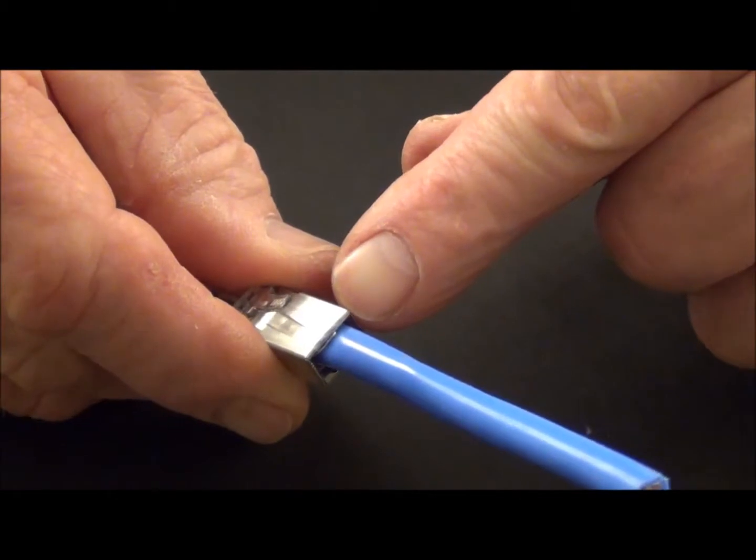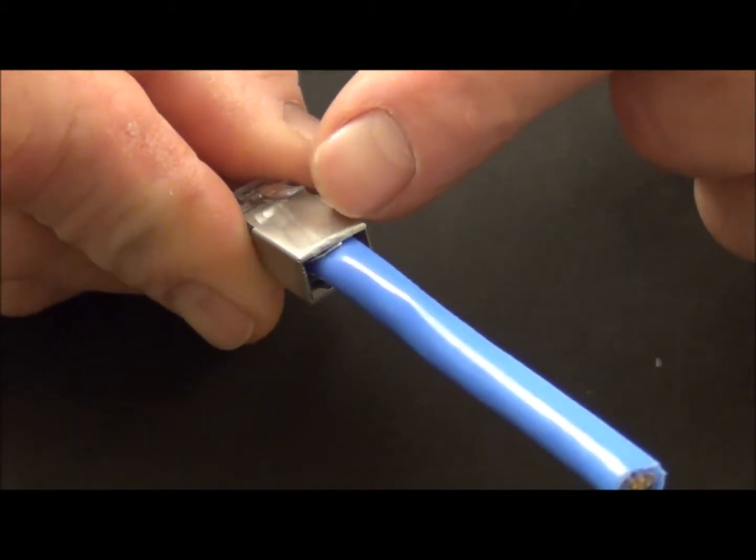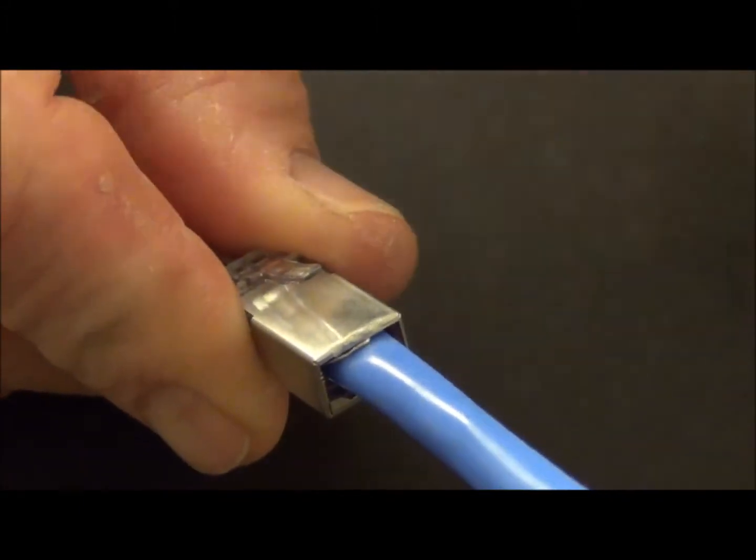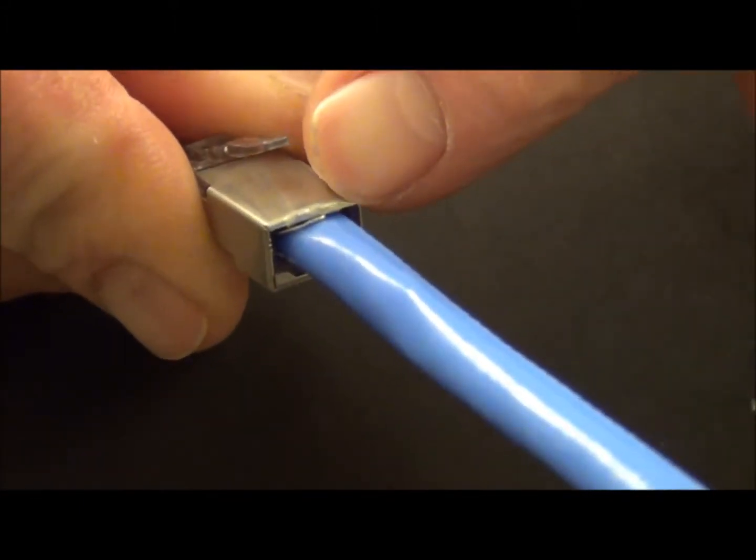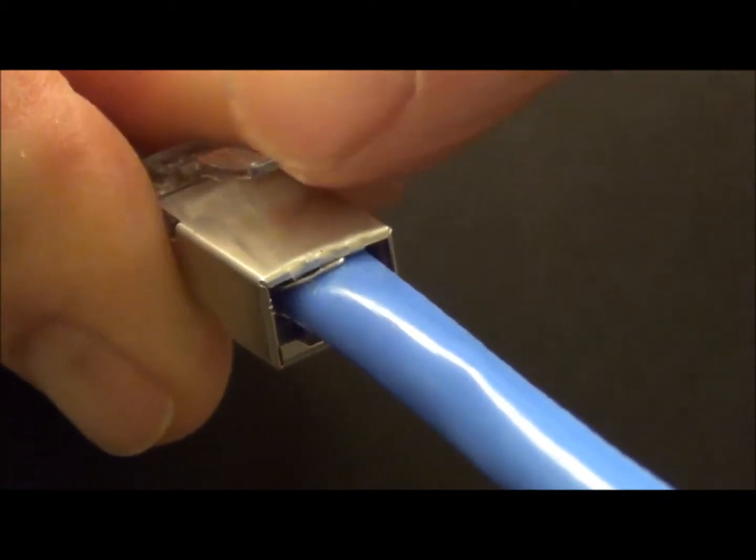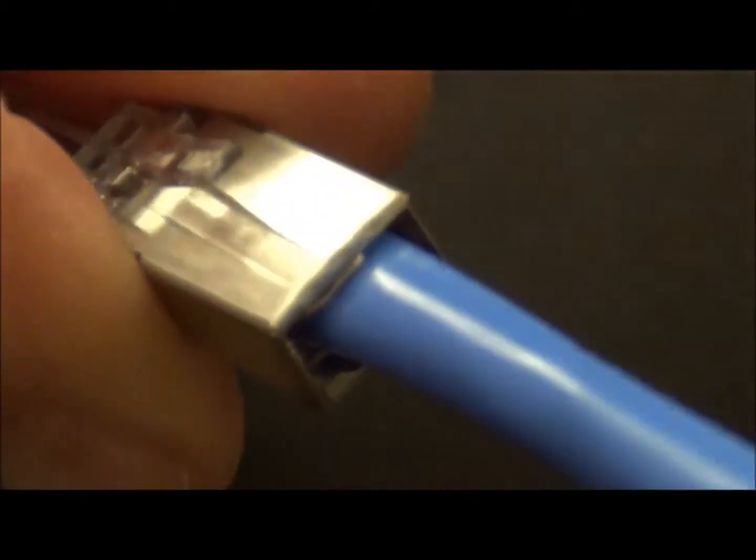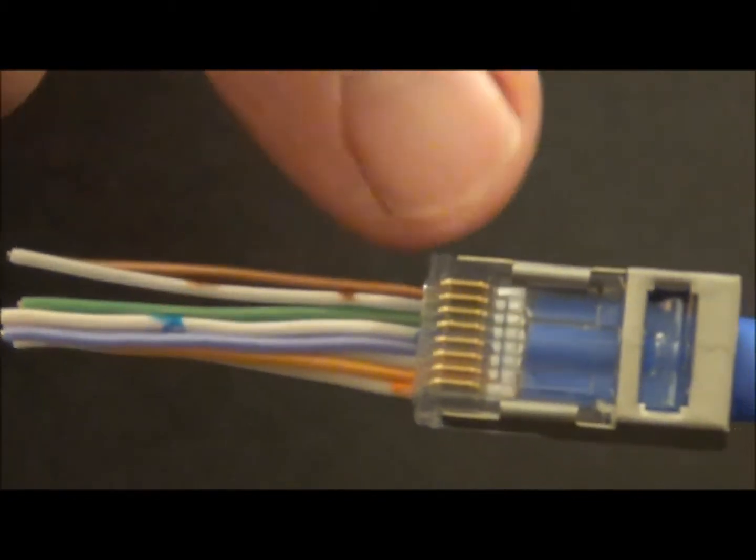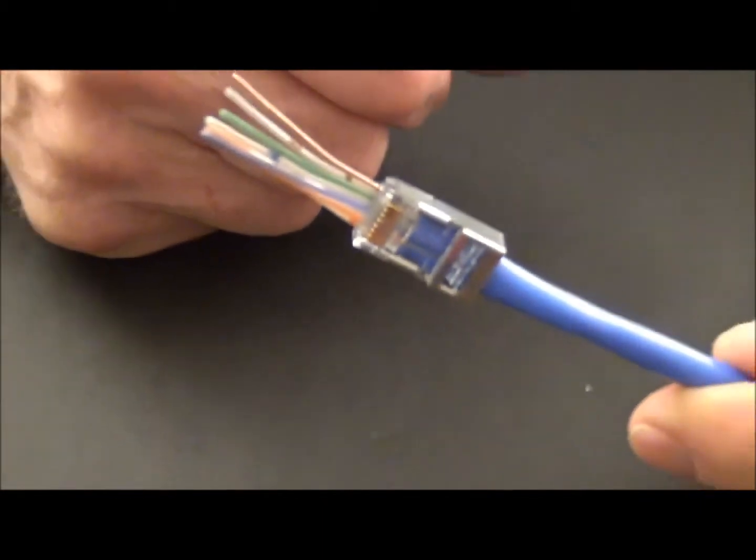Okay, here's the back end. You can slightly see my ground wire. I looped it and foiled it around. But you can see it right there at the back end. It's sitting really nice on those springs. It's going to be a good ground. And then am I going to meet Cat 6? Yes, I will. Because my twists, see the end of the jacket, are right there where they belong at the back of the contacts. So here we go, Cat 6, internal ground. Ready to be terminated.